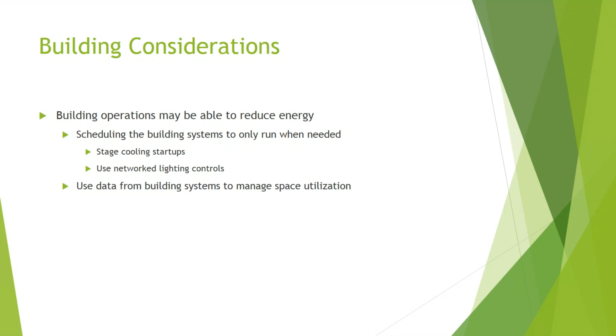Another aspect of building operations is using the data from the building systems to help manage the space better. There's a wealth of information available from most modern building systems. HVAC systems often have trending, however that trending is typically only set up for diagnostic purposes, so it might only record 18 to 24 hours of data and then start to overwrite it. That's useful for a facility manager to troubleshoot, but it doesn't really help you manage.